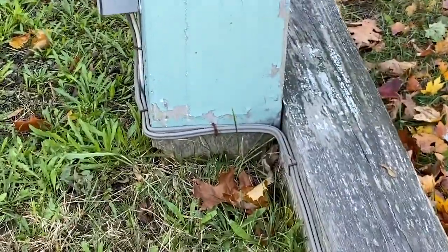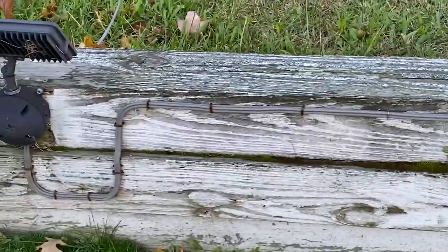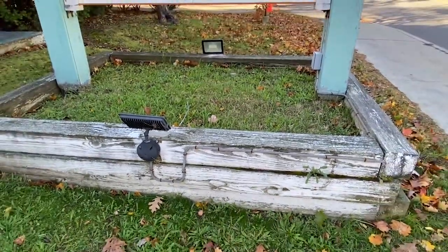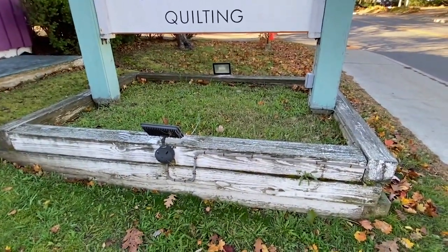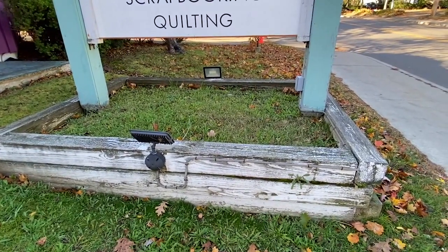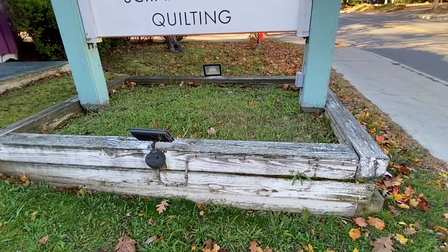The other problem is this cable may be exposed to physical damage. UF is not supposed to be installed where it's exposed to physical damage. That's a violation of 340.12 number 10. Russell Blank, NEC Consultant for EC&M Magazine.